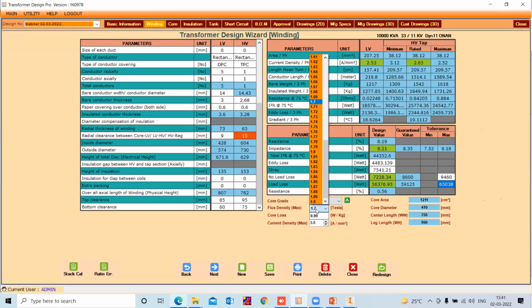Same with the flux density. If you have any specific value by customer, you can keep that value as a maximum and design the transformer. If your vendor or core manufacturer is different, you can edit these core losses according to your vendors. The maximum current density option is available to edit.